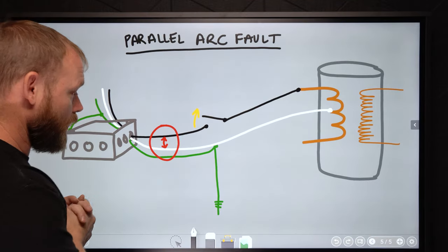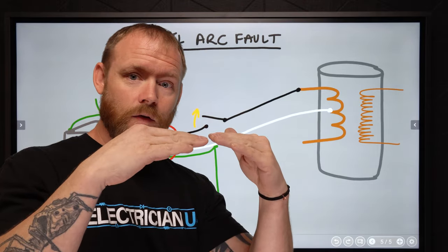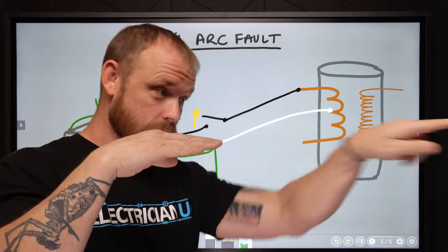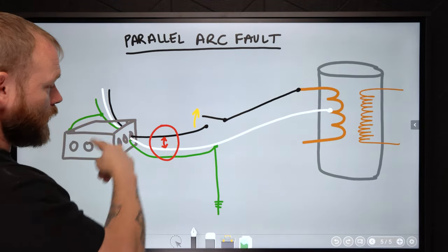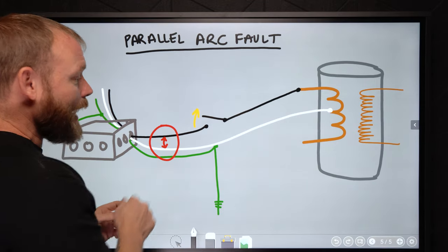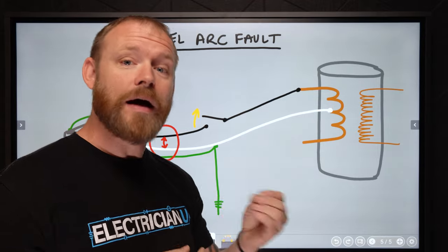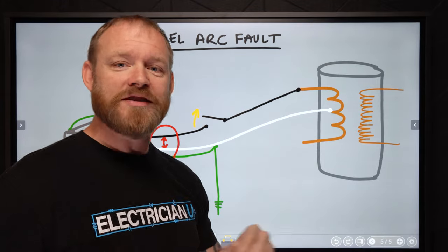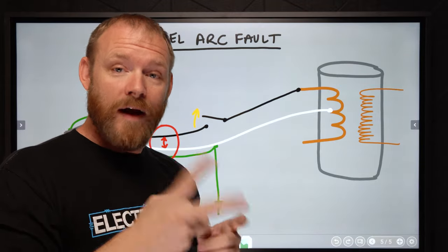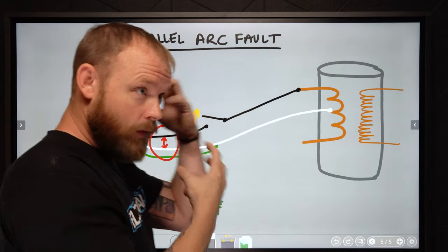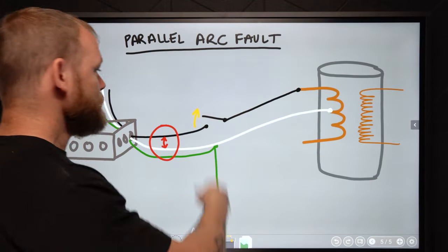A parallel arc fault is similar but occurs between two parallel conductors — for instance, arcing between a hot and a neutral. Combination arc fault devices detect both series and parallel arc faults — 'combination' doesn't mean ground faults and arc faults, it means both types of arcs. The breaker's electronics identify the signature of a parallel arc and open the circuit accordingly.